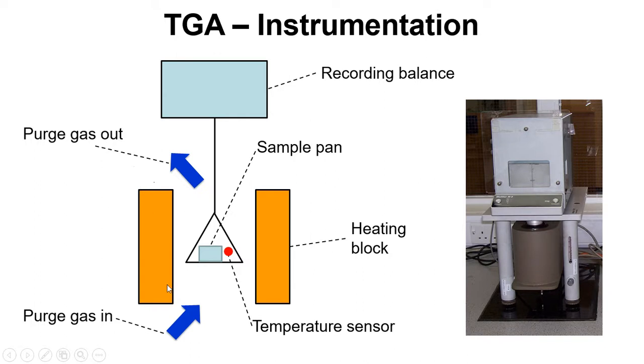We have the furnace or heating block that's warming this up, and we have a purge gas to carry away any gases that are coming off the sample.